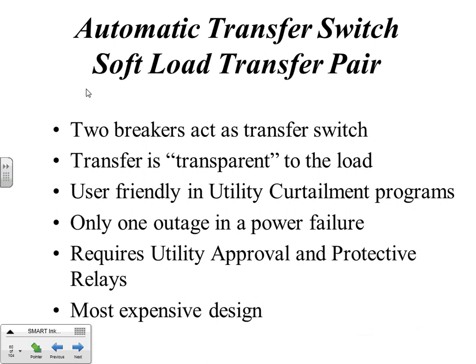All right, the final one I'm going to show you here is a common one. It's an automatic transfer switch using a soft load transfer pair. This is actually breakers. Two breakers act as the transfer switch. And in a soft load design, the transfer is transparent to the load. It doesn't know anything happened outside of a power failure, obviously.